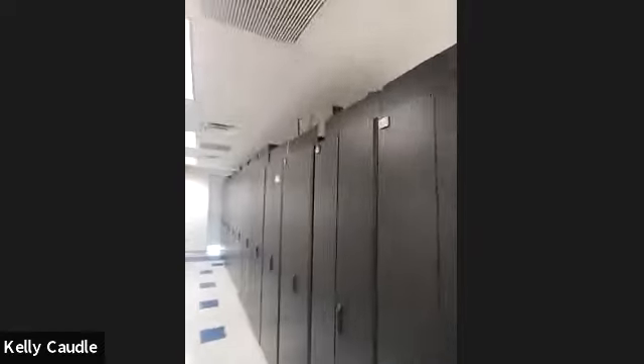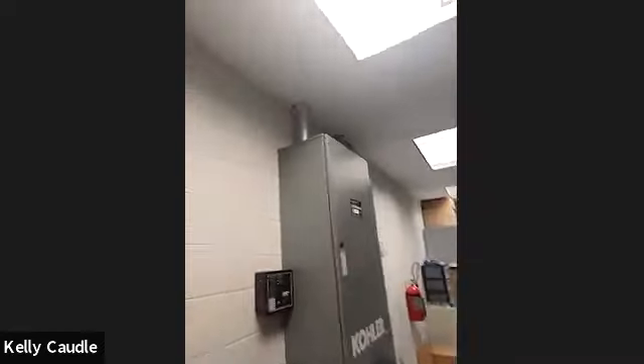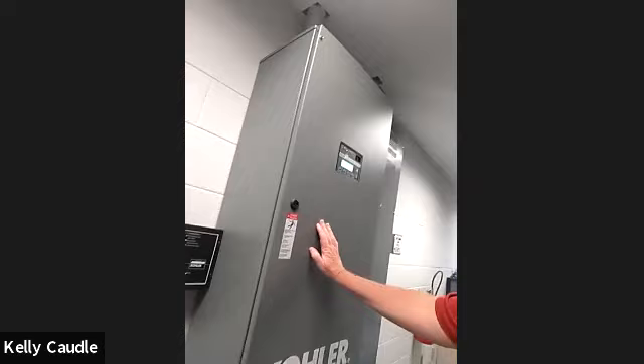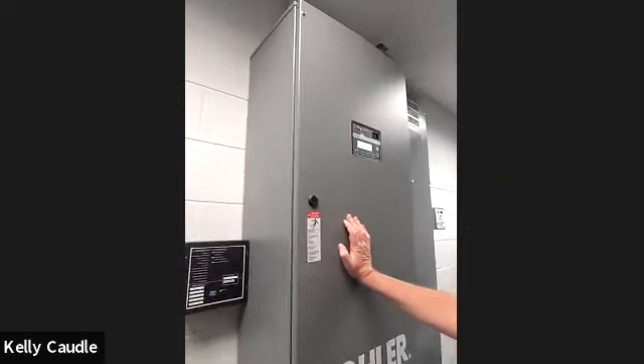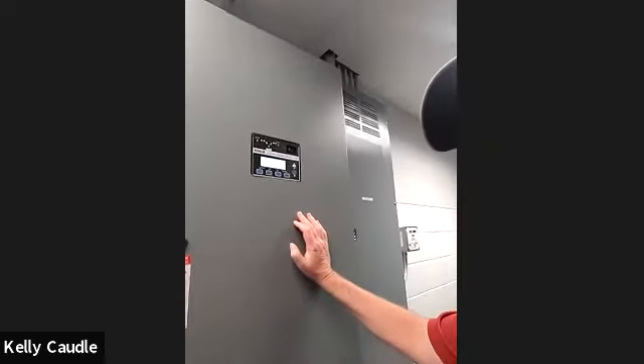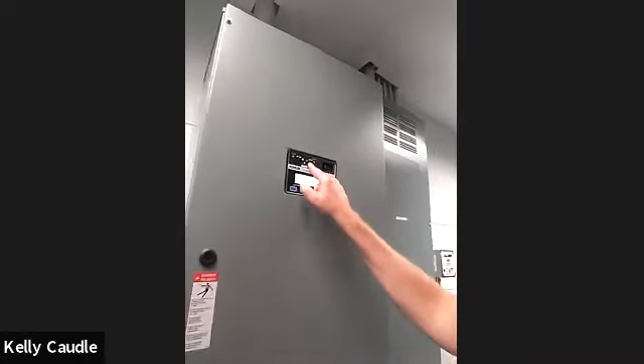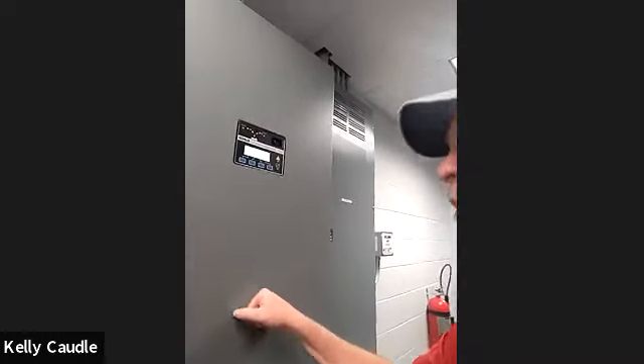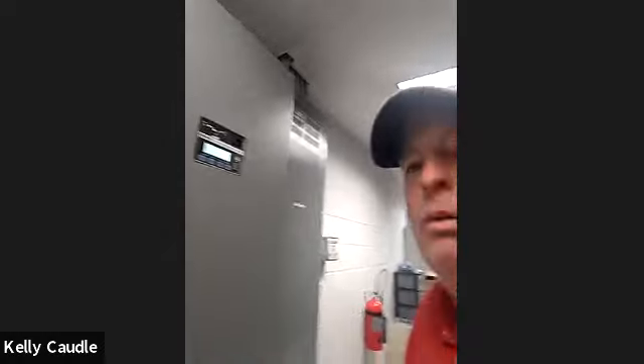So anything else you'd like to see about the data center? Back over here, if you've never seen a transfer switch, here's the transfer switch to a generator. This connects out to the generator, and if the power goes off, it makes a very loud popping noise, switches over the breaker, and the generator takes over immediately. It used to take over in less than 3 seconds, and that was so fast it was tripping a breaker, so we had to set it to be a little longer.